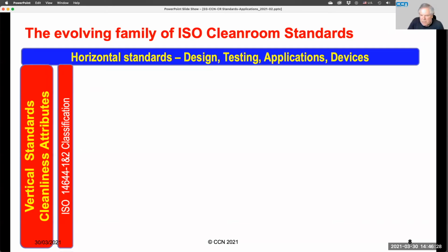So the core standard around which the whole sense of a clean room exists are ISO 14644 parts 1 and 2. Part 1 and 2 is classification of air cleanliness by particle number concentration. So it focuses on characterizing the cleanliness of a space by particle counting, particle number concentration, and it's this that enables me to call my space a clean room or a clean air device. So this is really the core. How I get there, how I design it, and what other aspects I test will be adjuncts to this fundamental classification.